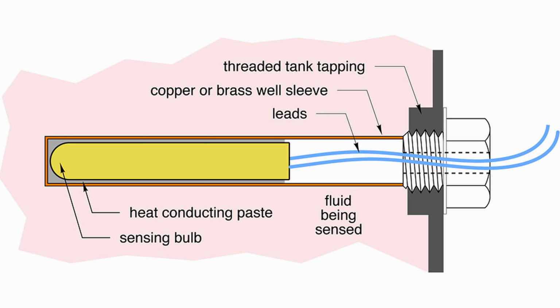So we have an issue here. The temp sensor that I'm using is a thermistor style 2-wire temp sensor, which means these 2 wires extend into the probe that touches the actual oil, and there is a variable resistor between the 2 wires. As the oil heats up and cools down, this resistor will resist electricity either more or less, and that amount of resistance can be equated to a temperature.